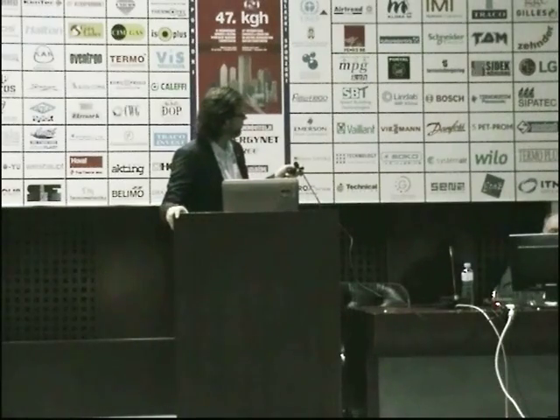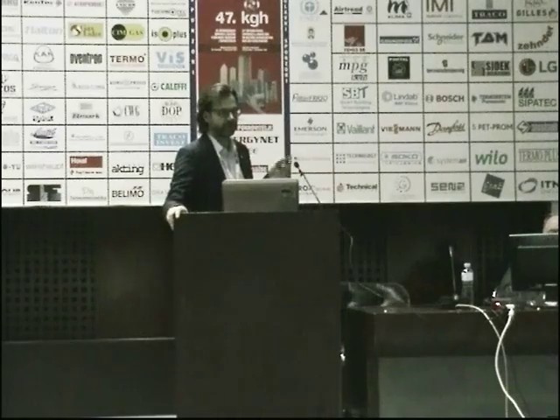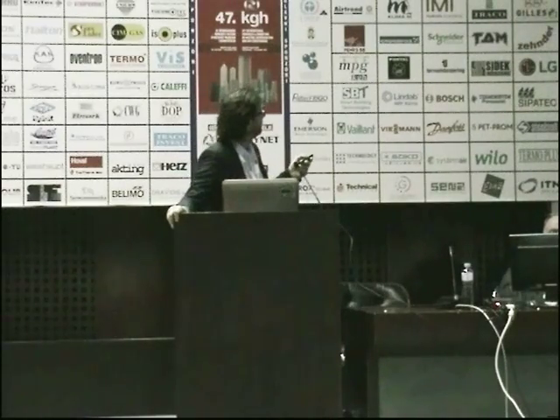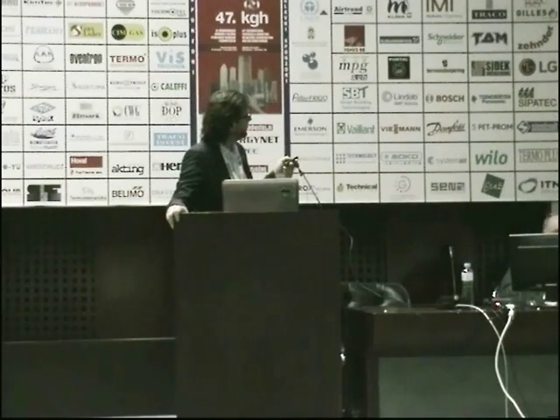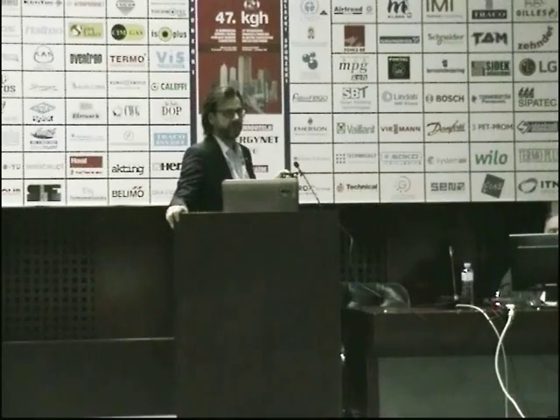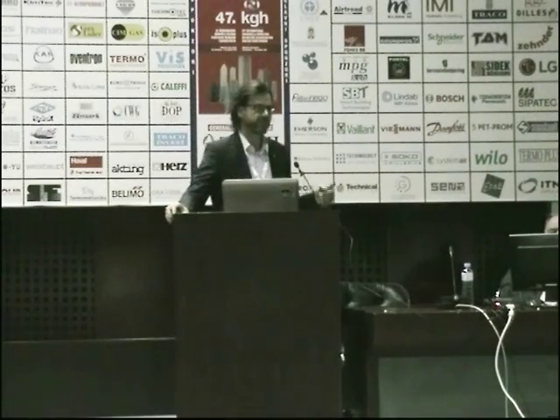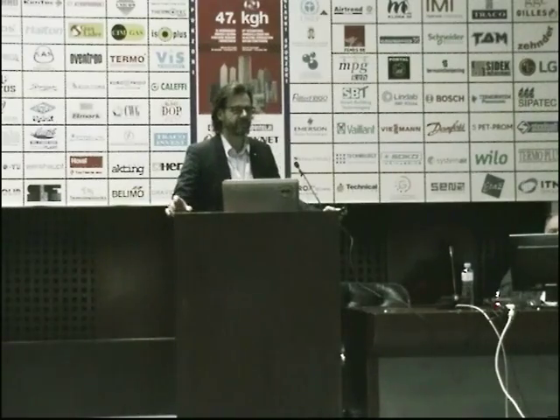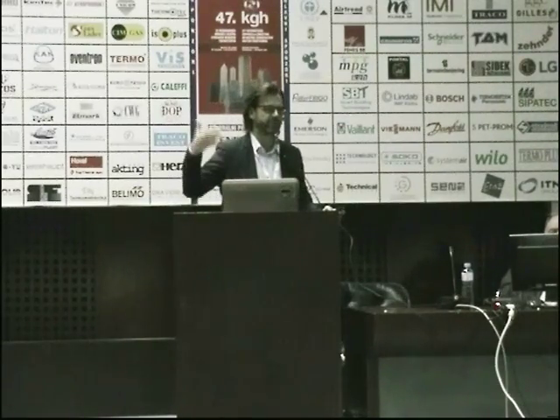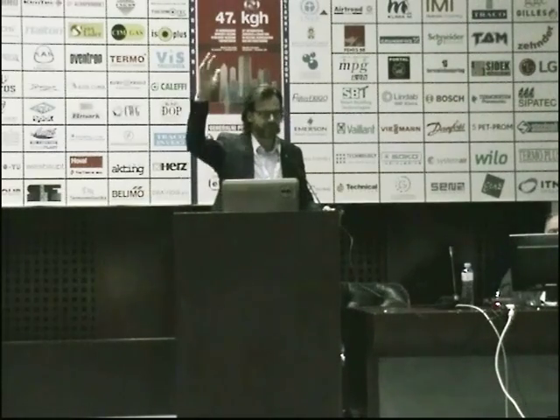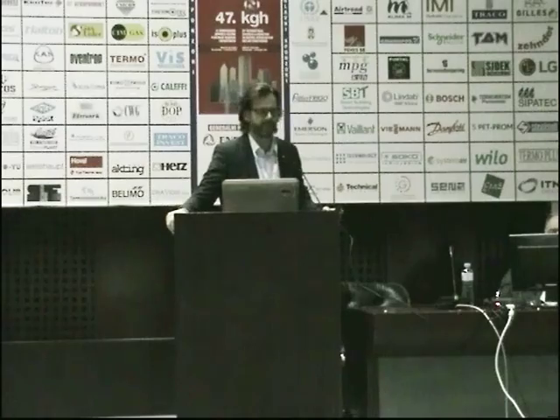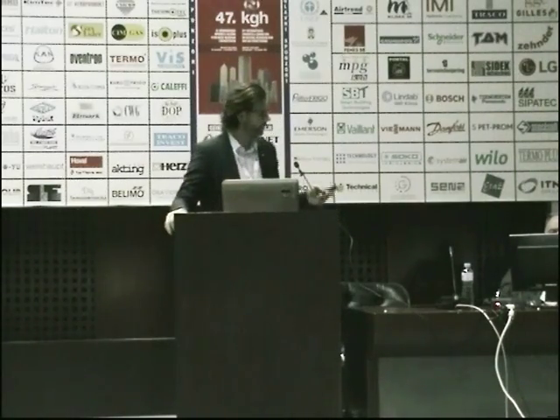Here you see what I mentioned before. The guys are making the pipework on the cabinets, and the people below are buying goods, vegetables or milk. We also see here the CO2 compressors for the site in Strand. One side effect was that we were implementing glass doors on the medium temperatures, which had not been done so much in South Africa. When I first visited, we had open freezer shelves without glass doors, 2 meters high, at minus 24 degrees. These were the older supermarkets. Now they use glass doors.